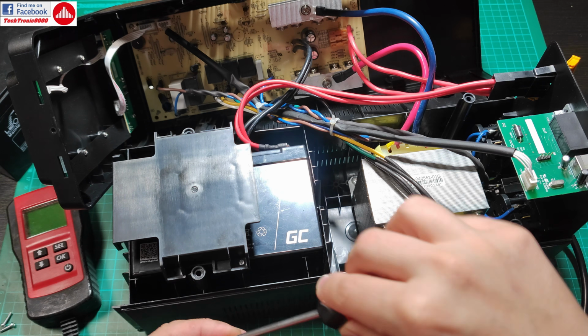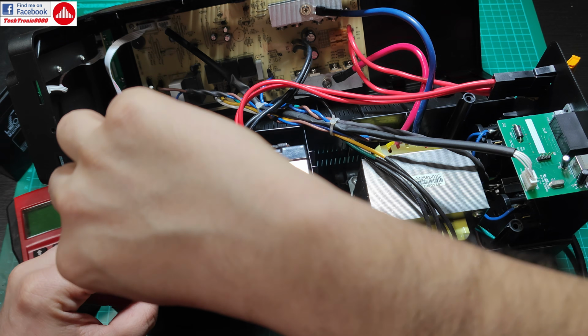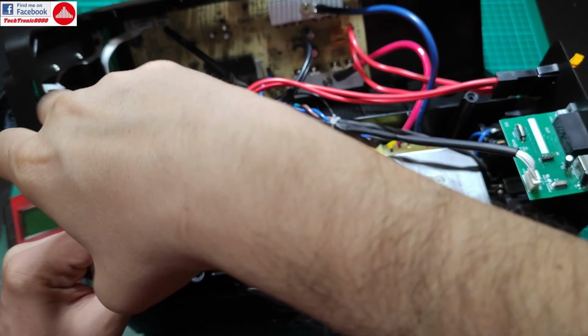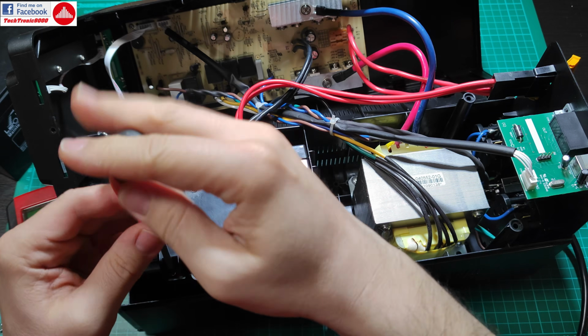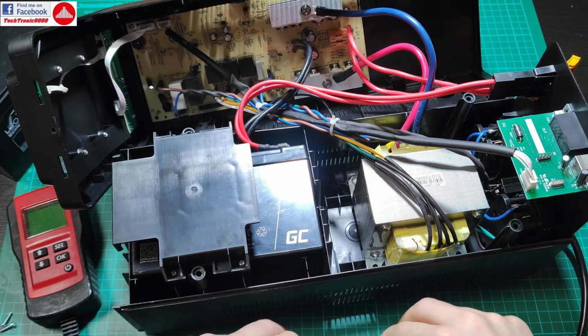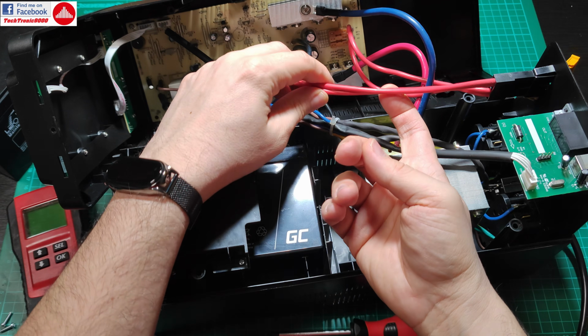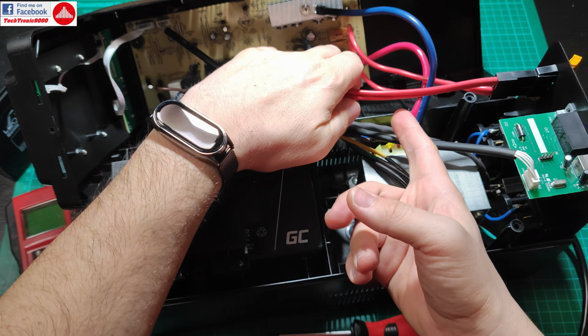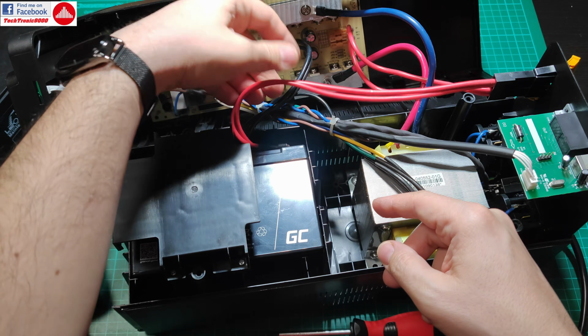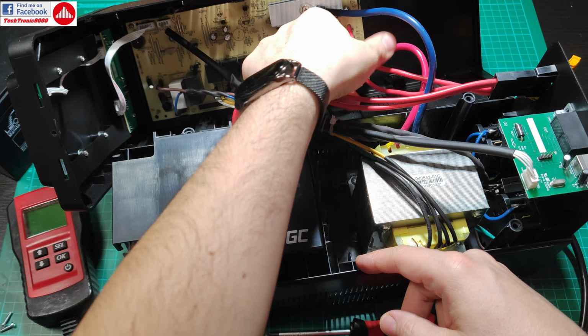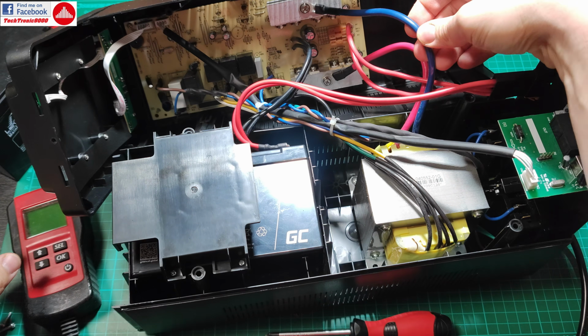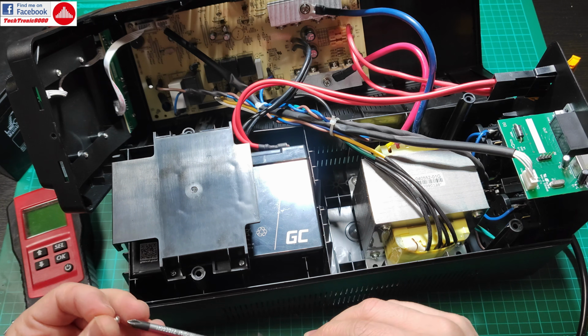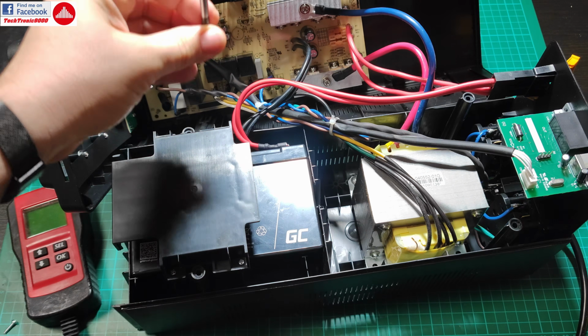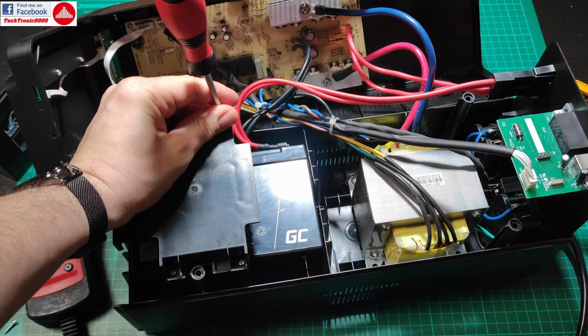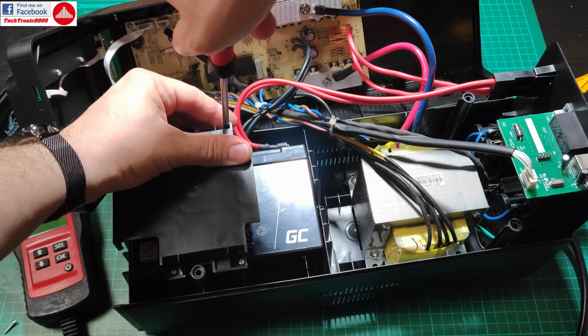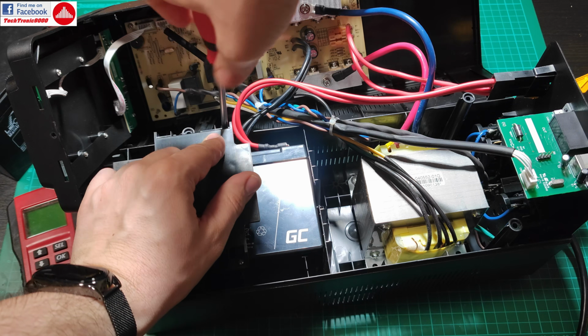That's very important because the current draw when the UPS is working is very high, so you need very good contacts, otherwise it can overheat, you lose power, and bad things can happen. There's such a big amount of draw that instead of using one very thick cable, they've used 2 cables for each circuit. You can see the transformer wires which have higher gauge wire, and there are 2 also in the back. Don't forget this fuse is still disconnected, so we're doing this safely.